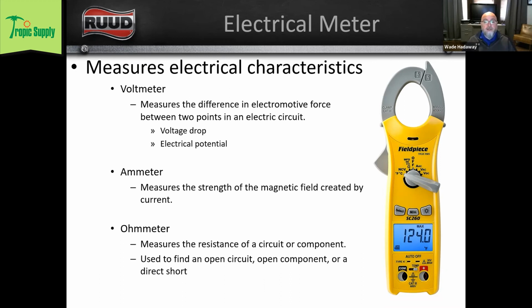And so our ohm meter measures the resistance of a circuit or component, and we can use our ohm meter to find an open circuit, or open component, or a direct short. I don't think I had a slide of a direct short. When we think about the path of the current in our electrical circuit, we've got a power source, we've got a control, and we have a load. If we have a completed circuit without having a load in there, that is called a short. That short will send voltage right back to whatever component it is, a board, a transformer, a breaker panel, and it'll cause an electrical short, and it'll blow a fuse or trip a breaker.